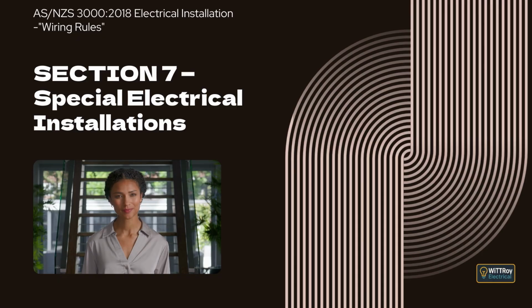This clause explains that Clause 7.5 applies to installations operating at extra low voltage and that compliance with this clause is taken as compliance with basic and fault protection requirements. Clause 7.5.2, Application. This clause explains that extra low voltage installations must be either SELV or PELV systems. It explains that the requirements of this clause supplement or replace other section requirements, and that where an installation operates at extra low voltage but does not meet SELV or PELV requirements, it is treated as low voltage and must comply with other relevant sections.